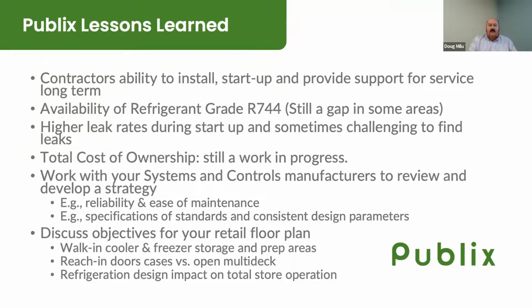I had a note about walk-in cooler and freezer storage prep areas. One thing we learned as part of our redundancy checklist is that we wanted diversity within the systems. Our liquid overfeed system kind of pigeonholed us into one rack system for the entire low temp and medium temp systems. Even though those systems operate really well and we've dialed them in, there's still a redundancy issue - if I have a problem, I put everything at the store at risk.